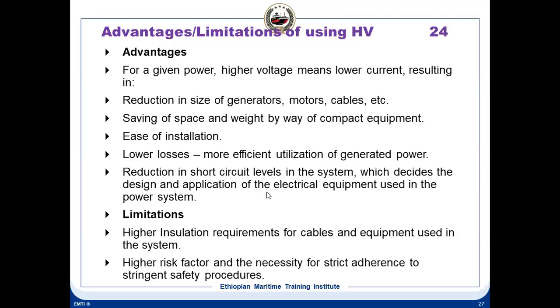It's not the size, because the insulation will become more in this case. That's why I want to tell you, the insulation will be more because of the high voltage: instead of 440, you're sending 6600. So it will have more insulation. So the cable thickness, not the cable thickness, the insulation will become more. There is a saving of space and weight, and the equipment may be compact.